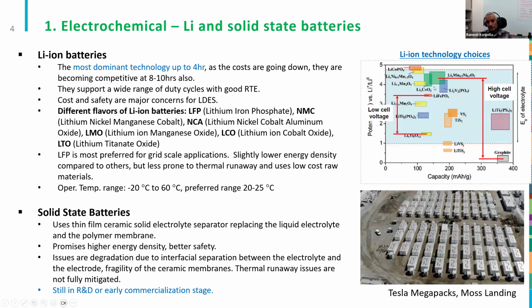But for energy storage, the industry is moving towards LFP. It has slightly lower energy density, but it's much safer compared to other lithium battery technologies, less prone to thermal runaway. They can theoretically operate over a wide range, but preferably within a certain range. If you go to very low temperature, efficiency is not as good. High temperature is also not as good because it's already hot and you need to dissipate heat, otherwise it gets too hot. So you need to put them in an air-conditioned enclosure, or a battery cooling system is needed to keep the battery in the safe operating zone.